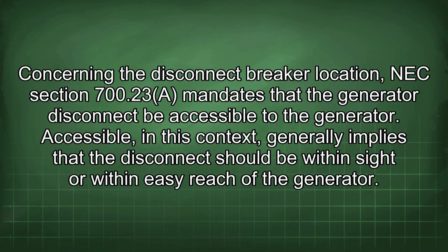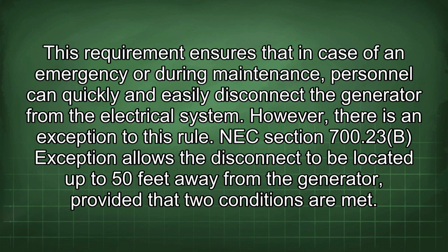Concerning the disconnect breaker location, NEC Section 700.23 mandates that the generator disconnect be accessible to the generator. Accessible, in this context, generally implies that the disconnect should be within sight or within easy reach of the generator. This requirement ensures that in case of an emergency or during maintenance, personnel can quickly and easily disconnect the generator from the electrical system. However, there is an exception to this rule.